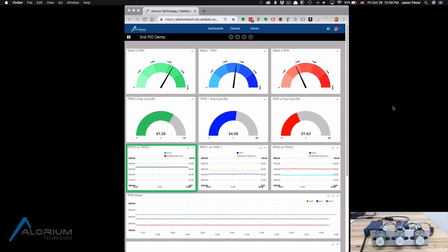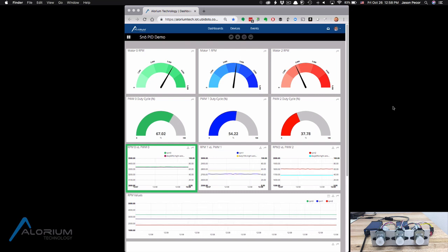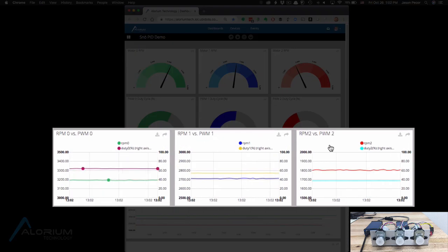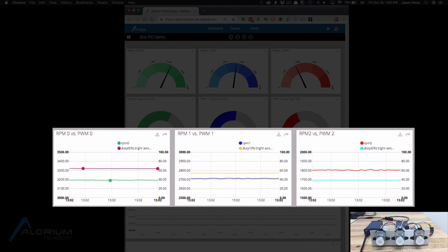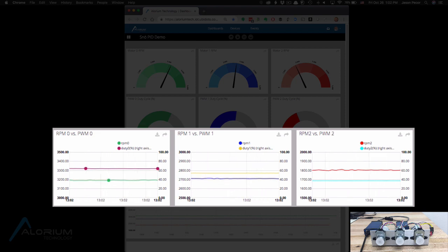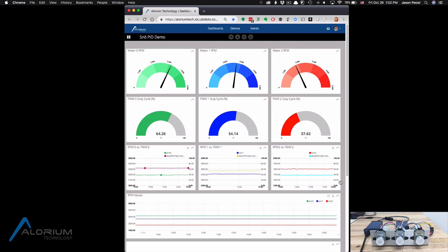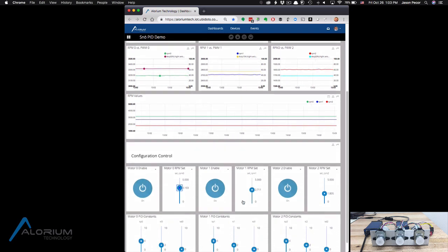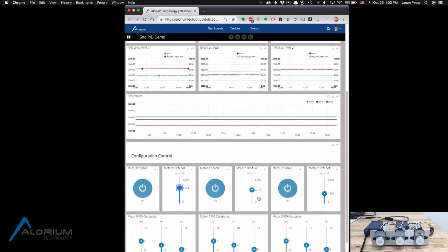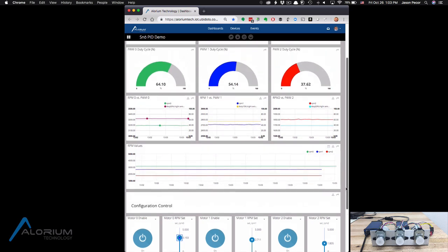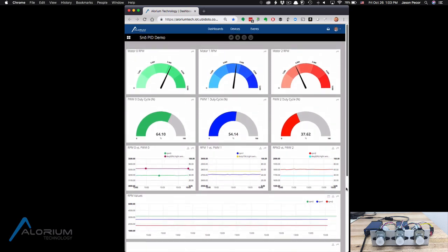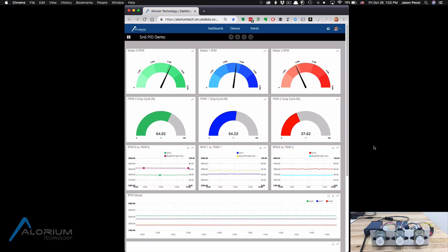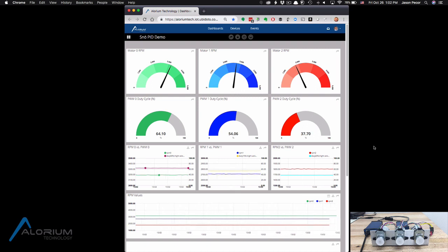In the case of motor 0, we're running at right around 3,300 RPM and the PWM is at 67%. We're going to focus on this row that shows the RPM values versus the PWM duty cycle because I want to demonstrate the PID in action. What the PID control loop is doing is keeping these motors at a fixed RPM value that we've configured down below in the dashboard. I'm going to apply some pressure to the spinning discs on the end of these motors and see if it can keep those RPM values where they're supposed to be.